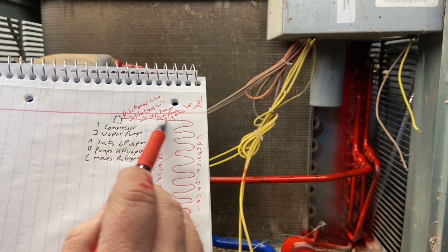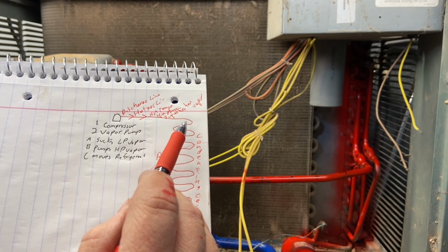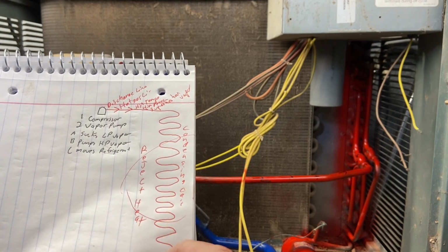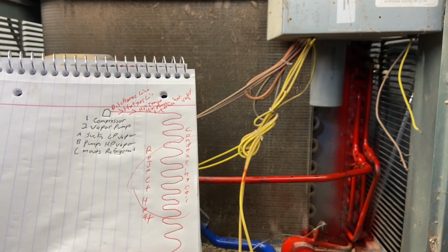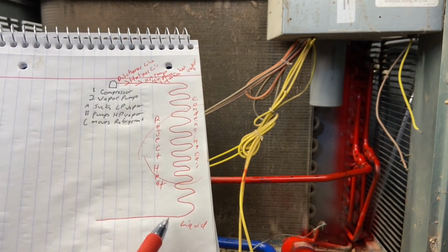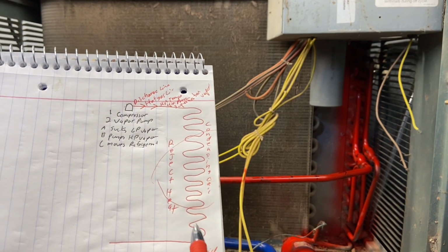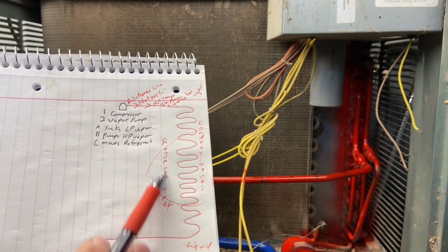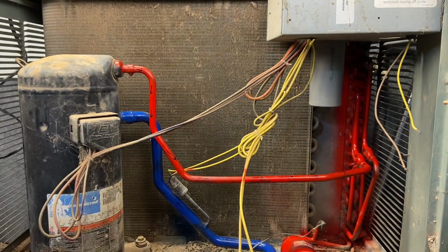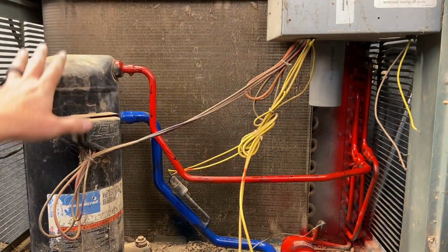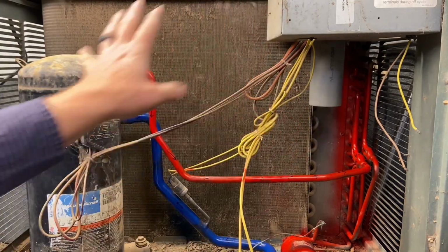Now we're going to be coming into this as a high temperature, high pressure superheated vapor. We're going to be coming out of this coil as a liquid. And we have several things to talk about before we get to that point. But we're going to go in as a vapor, come out as a liquid. It's actually condensing, which is why we call it a condensing coil. But right now, I just think of this whole thing as rejecting heat. Together, the compressor, discharge line, and the condensing coil, we call the condensing unit. Together, they make a unit.